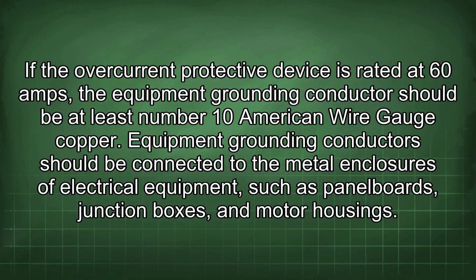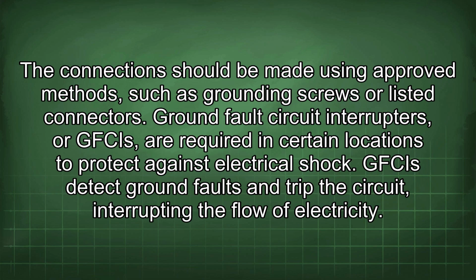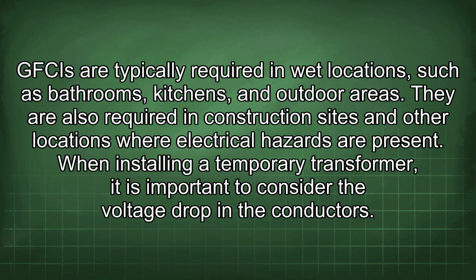Equipment grounding conductors should be connected to the metal enclosures of electrical equipment, such as panel boards, junction boxes, and motor housings. The connections should be made using approved methods, such as grounding screws or listed connectors. Ground fault circuit interrupters, or GFCIs, are required in certain locations to protect against electrical shock. GFCIs detect ground faults and trip the circuit, interrupting the flow of electricity. GFCIs are typically required in wet locations, such as bathrooms, kitchens, and outdoor areas. They are also required in construction sites and other locations where electrical hazards are present. When installing a temporary transformer, it is important to consider the voltage drop in the conductors.